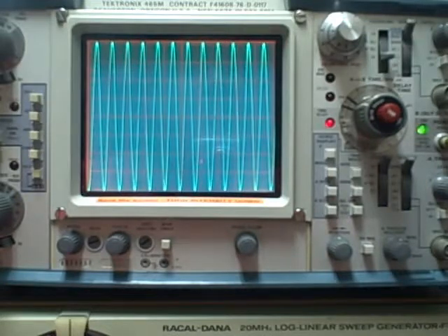And the 5200A is an RMS unit. So in order for me to provide 20 millivolts peak, I had to provide 14.14214 millivolts RMS. So I've already calculated what the RMS values necessary to give me the peak readings are, and I'll cite them as we go along.